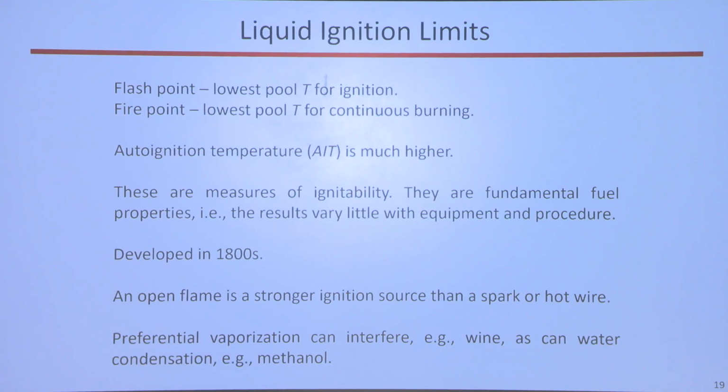So here's some factoids about liquid ignition limits. The flash point is defined as the lowest temperature for a temporary flame, intermittent flame, and the fire point is the lowest point for which you can have a continuously burning flame.